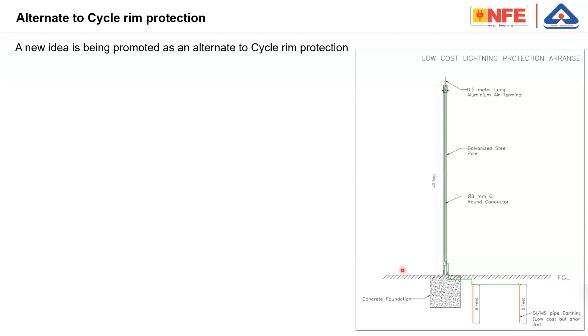Recently, we saw another method which is claimed to be an alternate, as per IS/IEC 62305. The claim that it is as per IS/IEC 62305 is also not correct. You see a metal pole instead of a cycle tire and a wooden pole. There is a 13 meter long metal pipe connected to two earth electrodes, as you can see here. And the claim is that it protects a 45 degree shadow area.